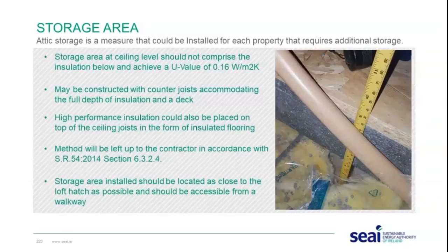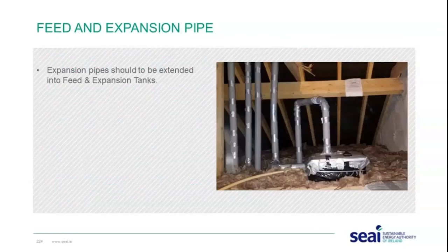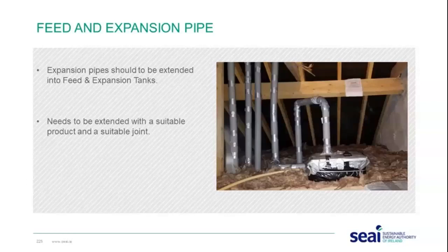The storage area should be installed as close to the loft hatch as possible and accessible from a walkway. For feed and expansion pipes, these should be extended into the feed and expansion tanks. Situations arise where contractors have not properly extended the pipe into the tank, or have used pipe insulation to extend it rather than the pipe itself, or cut a square out of the tank — these approaches are not acceptable as there is no guarantee that boiling water would enter the tank without spilling out.